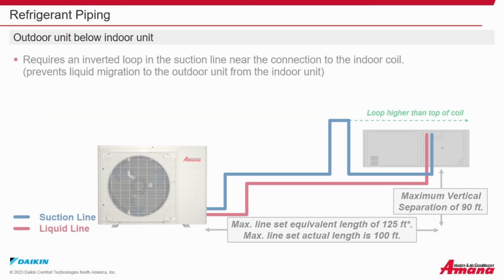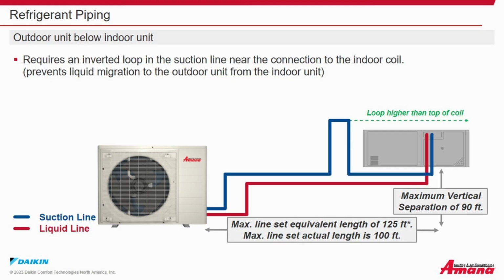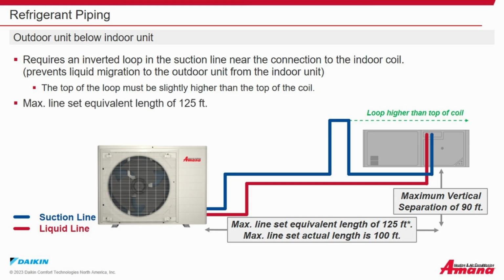When the outdoor unit is located below the indoor unit, it requires an inverted loop in the suction line near the connection to the indoor coil. This prevents liquid migration to the outdoor unit from the indoor unit. The top of the loop must be slightly higher than the top of the coil. Maximum equivalent line length, 125 feet, which includes pressure losses of any elbows, bends, etc. But the maximum actual line length is 100 feet. Maximum vertical separation in this case is 90 feet.